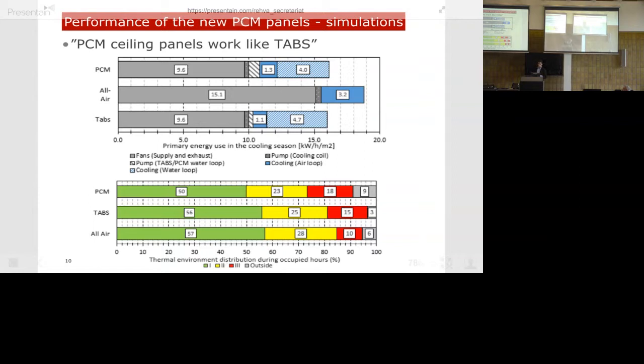These are the results you see. The first graph shows energy use for PCM, all-air, and TABS systems, conditioning the same office space for 24 occupants, with a room area of 53 square meters—so a very high cooling load. We can see that both PCM and TABS perform similarly in terms of energy performance, roughly 20% lower than all-air.